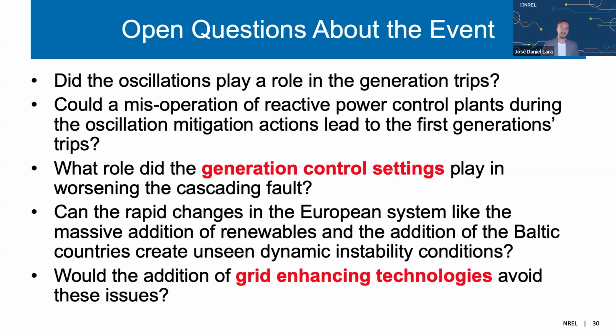For that, we require data on the actual controls of that machine, knowing which flag was the protection, which flag was used. Can the misoperation of reactive power control meant to mitigate the oscillation lead to the first generation trips? We also don't know this. Again, the operator was following the protocol of connecting more lines and connecting the STATCOMs to try to bring down the voltage, again changing the balance of reactive power through the system. We still don't know if that could have actually led to this first trip.